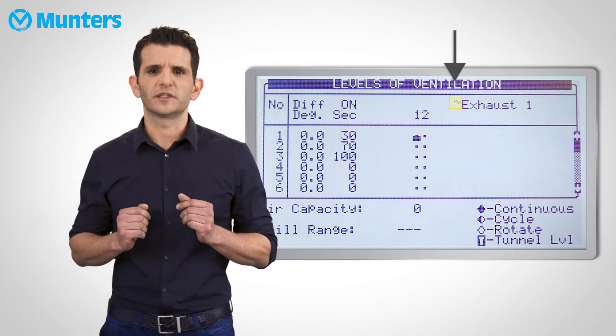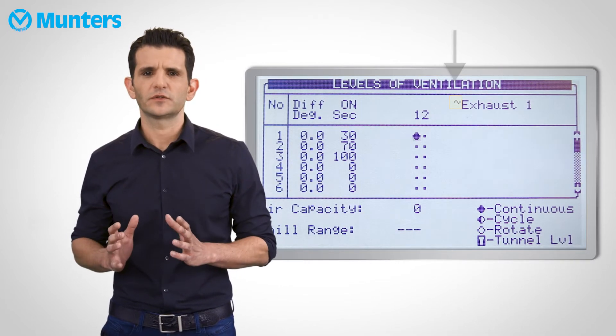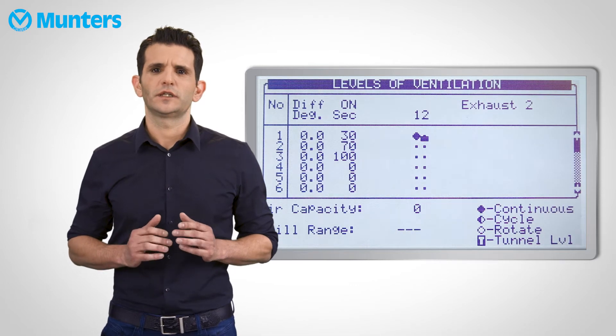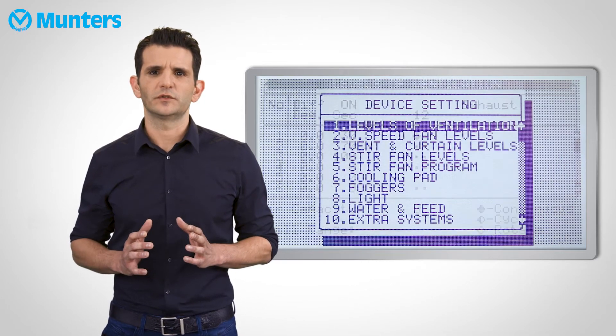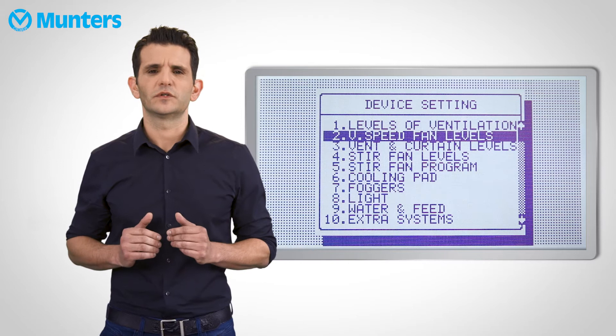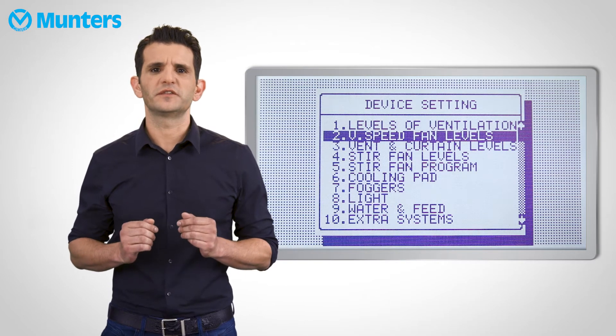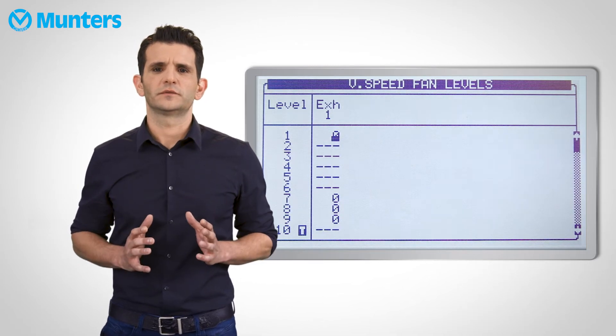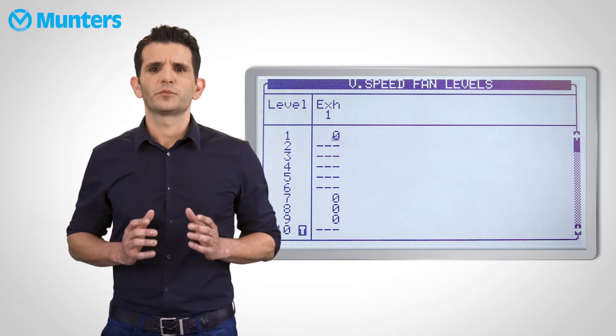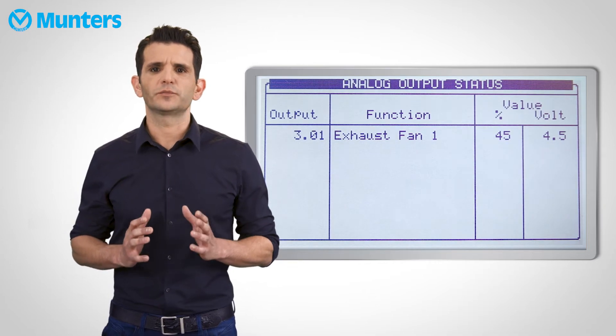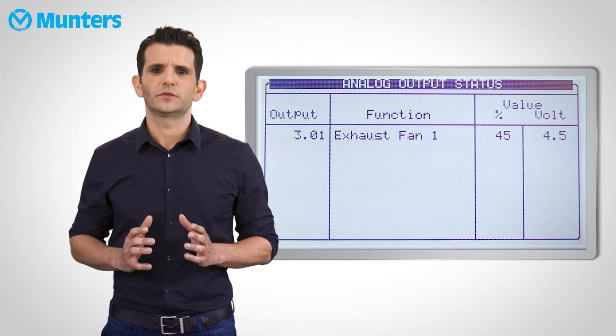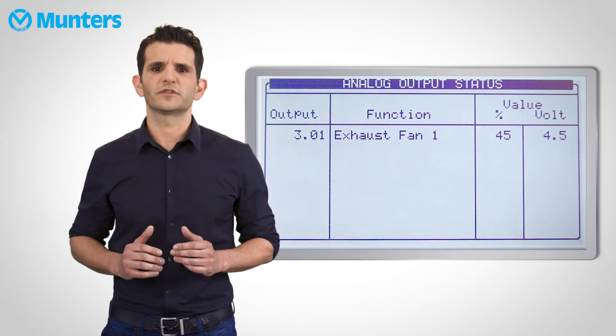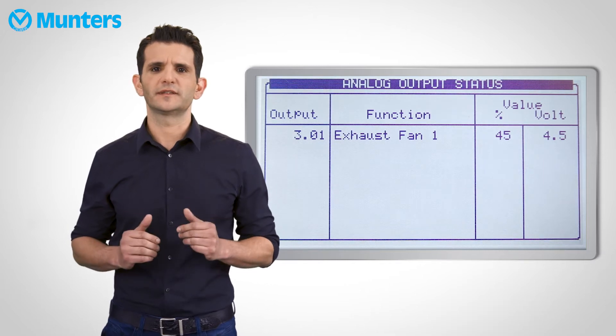This means that this fan is a variable speed fan. You can choose this fan to be continuous or a cycle. Now press Menu to exit this table, and select the second table, Variable Speed Fan Levels. Here you can select the speed of the fan for each level. Pressing 7 on the main screen will take you to the Analog Output screen, where you can view all the variable speed devices with their current intensity.